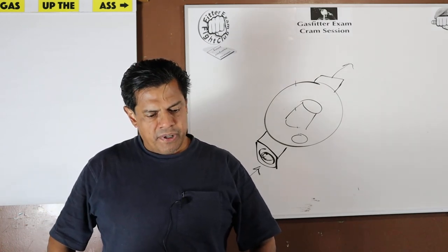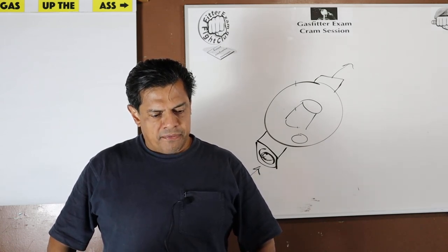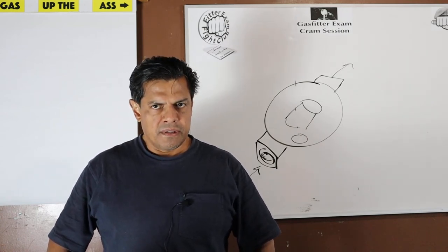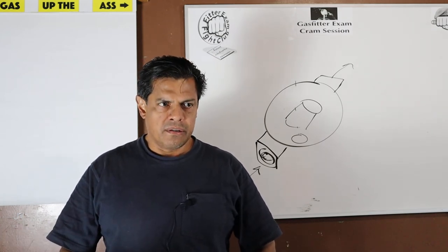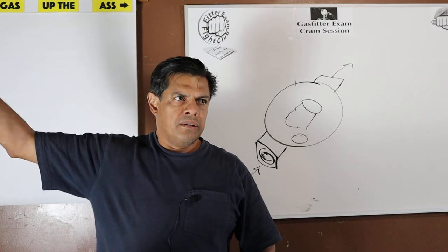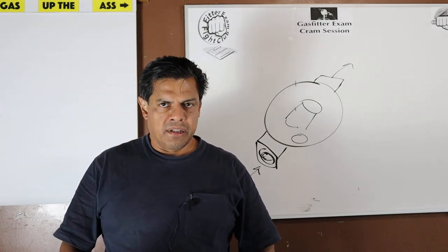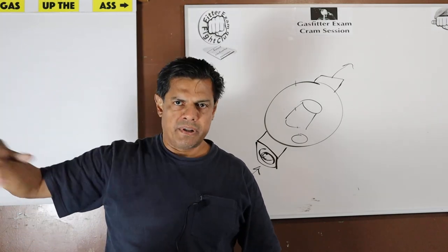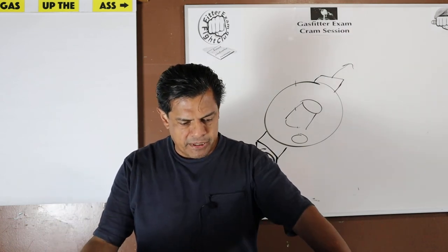Condensate lines from fuel burning gas appliances. So we're talking about fuel gas burning appliances, like HVAC units. Some units produce their heating or cooling, the cooling especially. Those coils will produce condensate, but if you're running the lines to take the condensate, the water that's produced from there, to some place of disposal, 3/4 inches internal diameter.